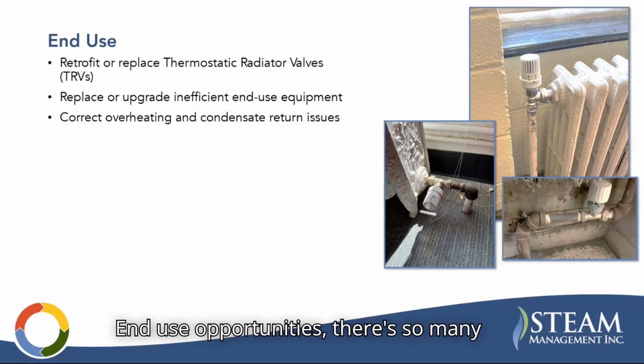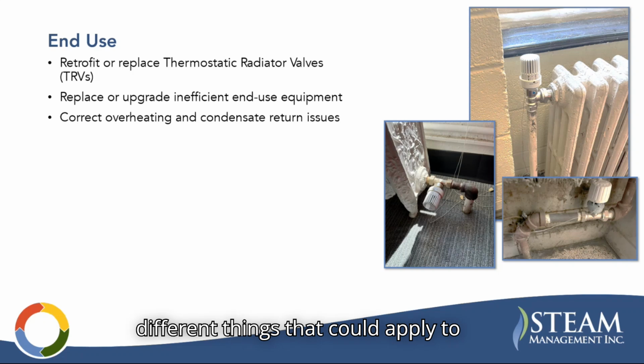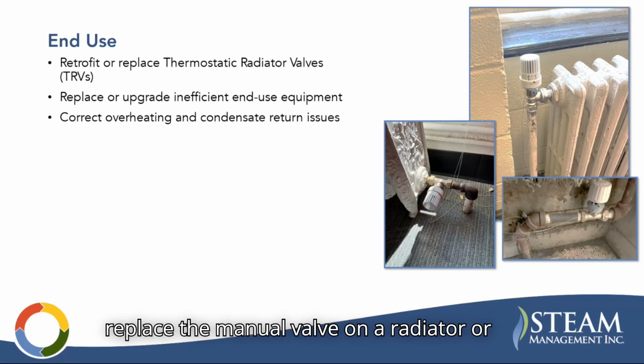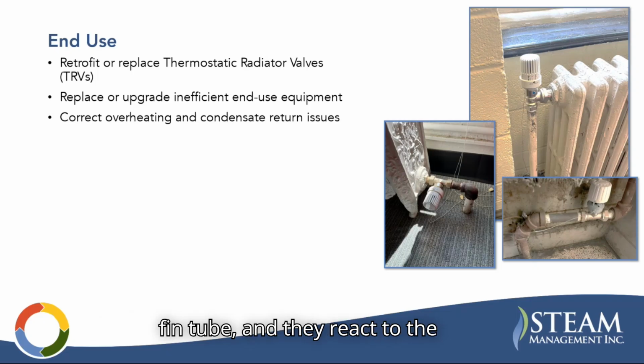End use opportunities. There's so many different things that could apply to this, but one big opportunity I did want to highlight is retrofitting or replacing thermostatic radiator valves. They're basically little control valves that replace the manual valve on a radiator or fin tube, and they react to the temperature in the space and regulate steam flow to the radiator. So they can really save a good amount of energy. I think 5% of that particular radiator's energy use is a typical rule of thumb. So those are a good opportunity and also a good tack-on if you're doing steam trap retrofits anyway.